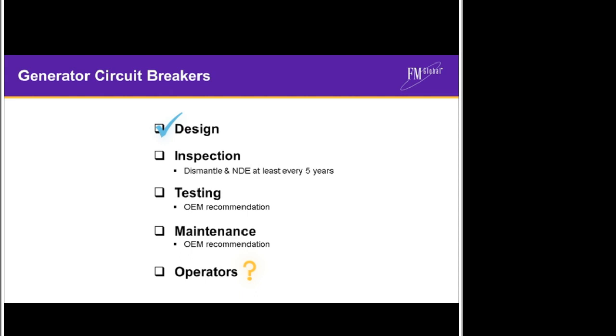The electrical grid can sometimes be overlooked as an energy source, but motoring events leading to catastrophic destruction of steam turbines account for some of the biggest losses in FM Global's history. From a design perspective, electrical switchgear, including generator circuit breakers, arrived at a good place some decades ago. The benefit of electrical reticulation systems is that by definition, there is redundancy included. Sometimes that redundancy includes tripping the rest of the plant or town, but the redundancy is nevertheless there.